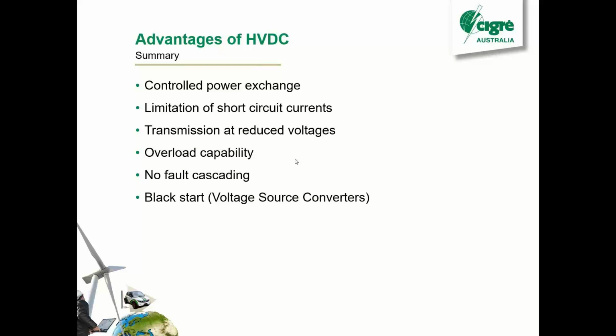With the HVDC, you can also do transmission at reduced voltages. So here in New Zealand, we normally operate at 350 kV, but we can operate at 250 if we want. And that can be handy if we've got problems on the line, like contamination on bushings, or where we're getting flashovers. We can just go to reduced voltage, and it restricts the power we can send, but at least we can still send something. Whereas with the AC line, it's either in or it's out, and you can't have sort of 50%.